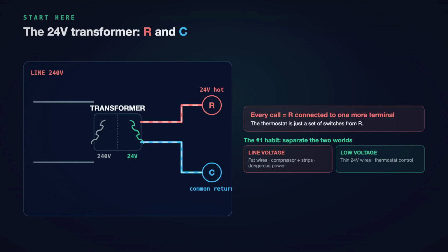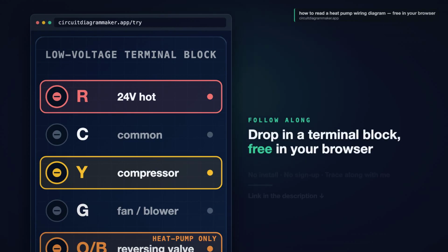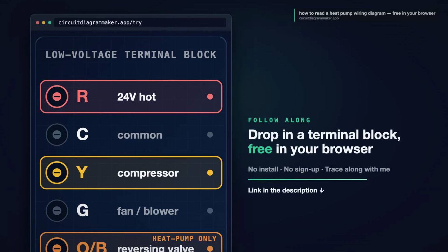And here is the single most important habit for reading any heat pump print. Separate the two voltage worlds. There is the line voltage side, the fat wires feeding the compressor and the heat strips with real, dangerous power. And there is the low voltage side, the thin 24-volt control wires running out to your thermostat. Trace them separately, and nothing on the page can confuse you.